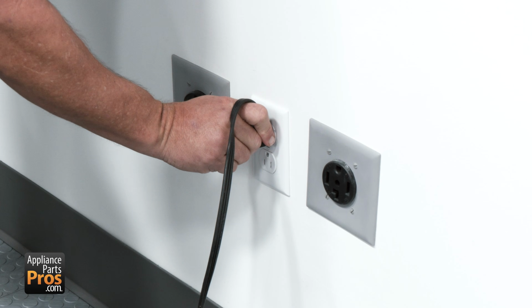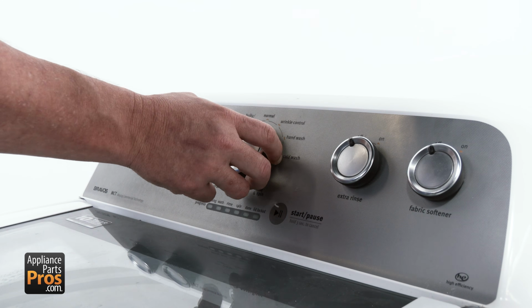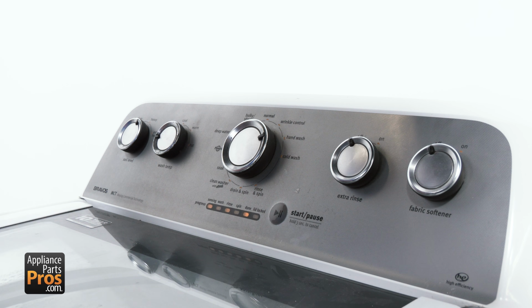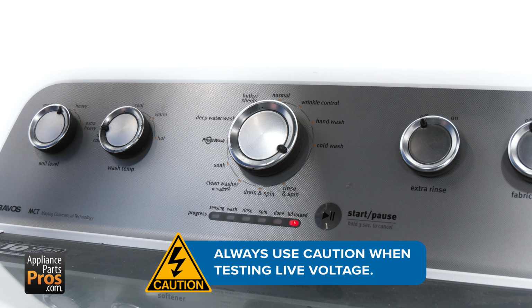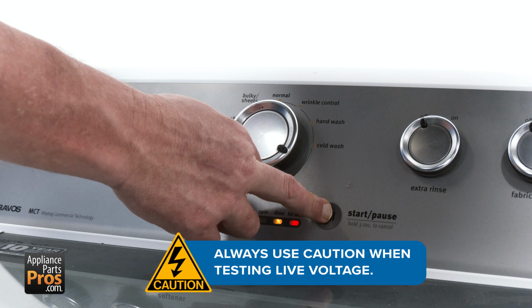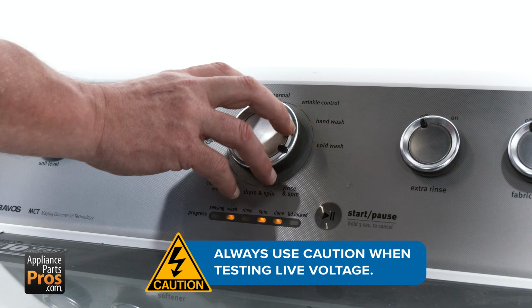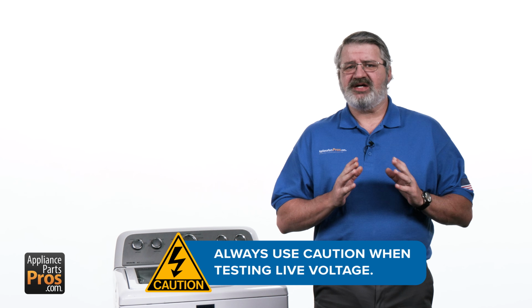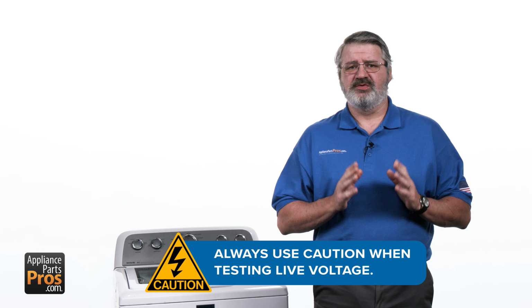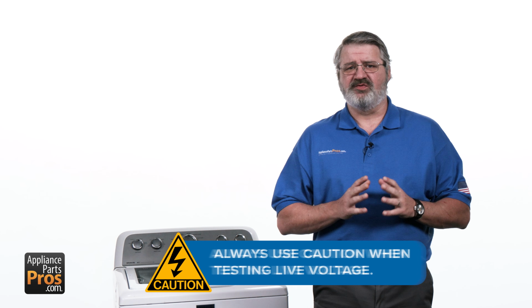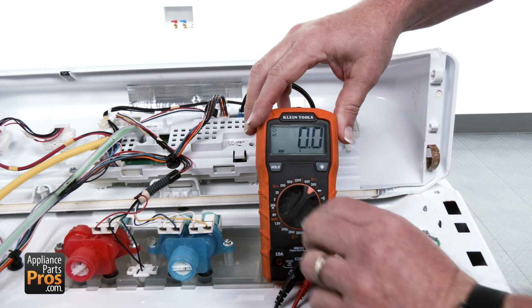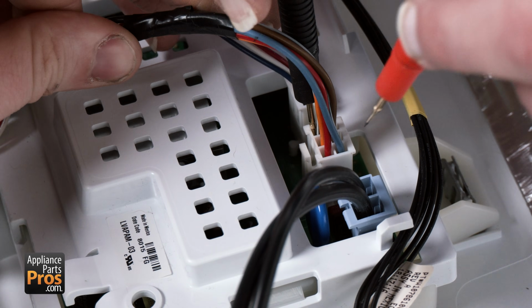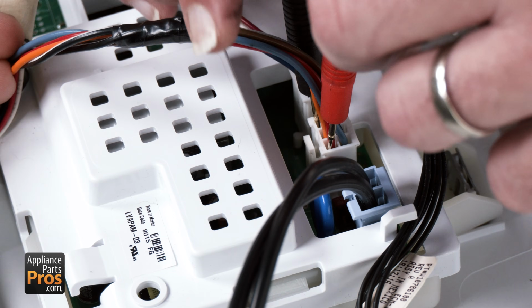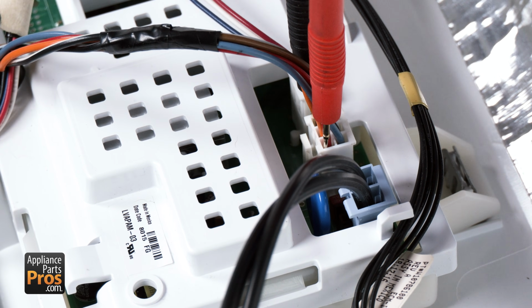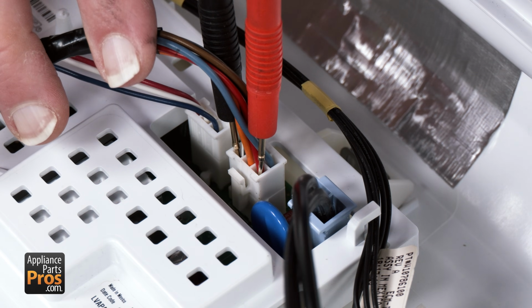After reconnecting power, start by entering the manual test mode and activating the gentle agitation test. Extreme care should always be taken to protect against electric shock, which could potentially result in serious injury. Please do not test line voltage if you're uncomfortable using a multimeter around live voltage. Set your multimeter to AC volts and place the black probe on J2 pin 4, line 1, and the red probe on J2 pin 6, clockwise winding.